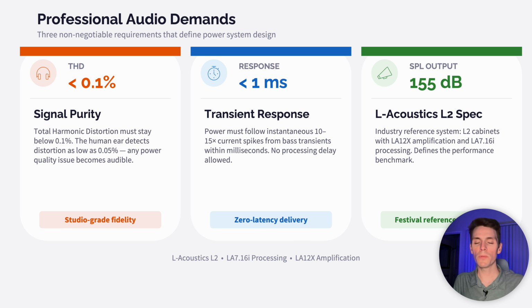The answer starts with professional audio. Festival sound systems have 3 non-negotiable requirements. First, total harmonic distortion must stay below 0.1%, and we notice distortion as low as 0.05%. Second, power must follow the instantaneous 10 to 15x current spikes within milliseconds. And third, the reference system, L-Acoustics L2, outputs 155 decibels. These 3 constraints define the entire power systems design.